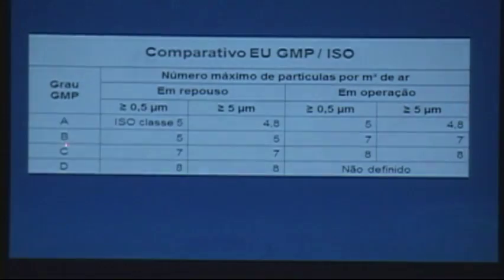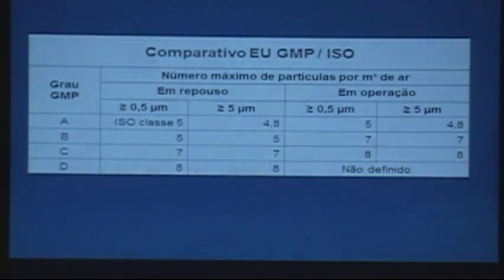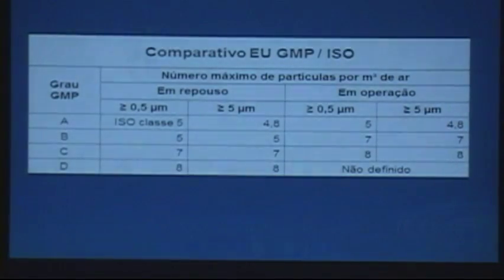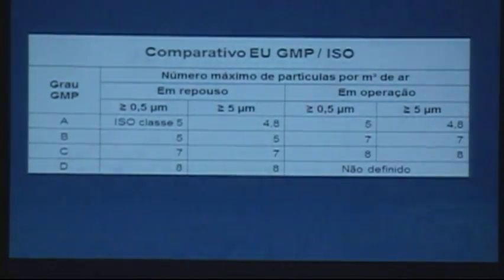I only achieve levels B and A with unidirectional flow — or a ceiling or an area within a room formed by absolute filters, EPA filters, or high-efficiency filters, forming a descending air piston — most of the time, though it can also be horizontal. But I can only achieve class 5 and GMP grade B and A in this way.